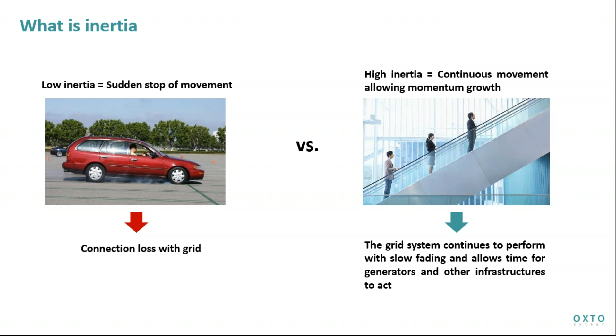This is what happened in the UK last year, and also in Australia, especially South Australia in 2016-17, when the whole region was blacked out during summer. That event drove the development of frequency response and inertia capability requirements for all non-synchronous generators. Similar issues have also occurred in the New York area in North America.